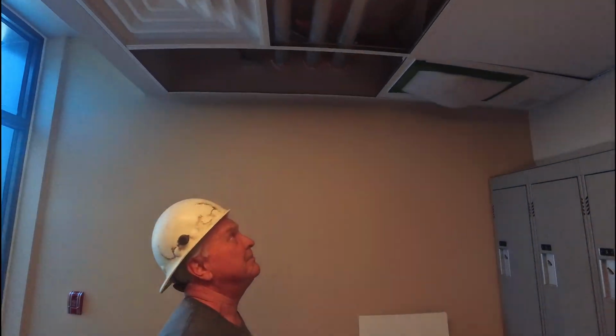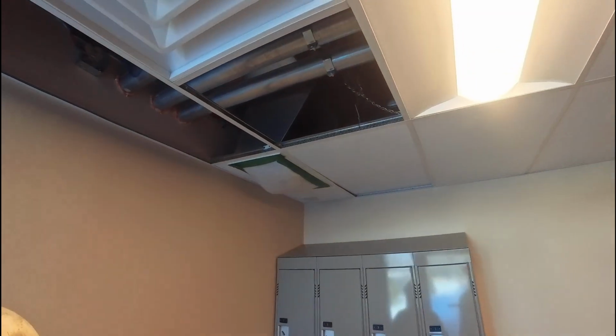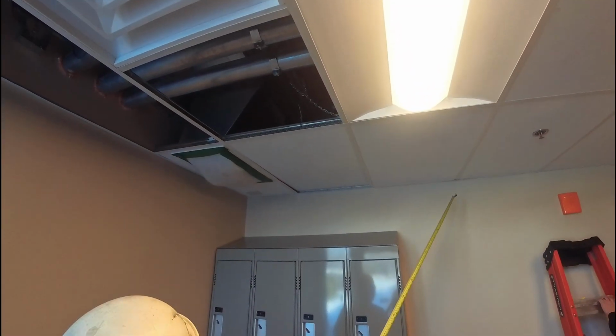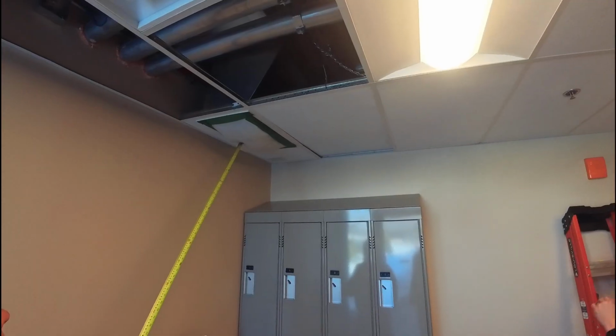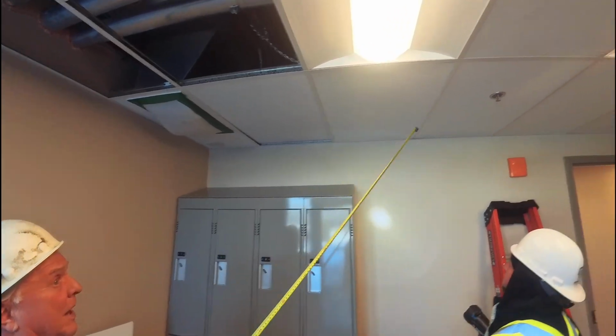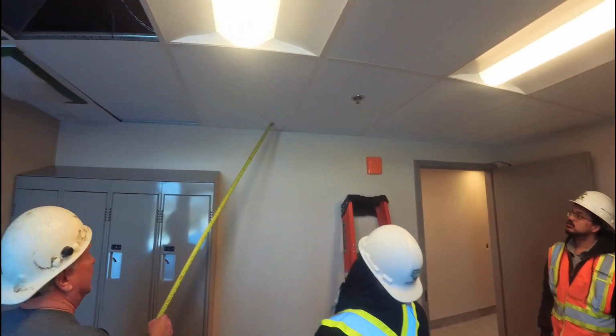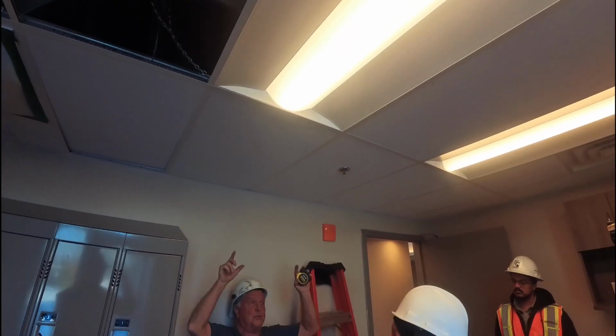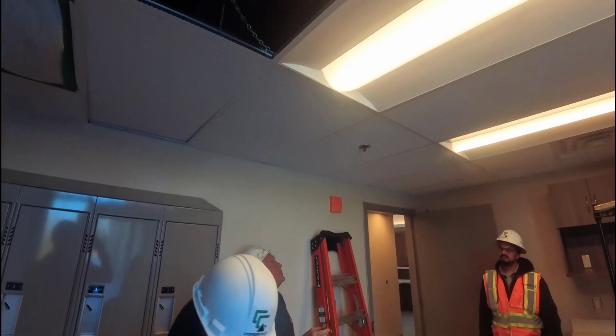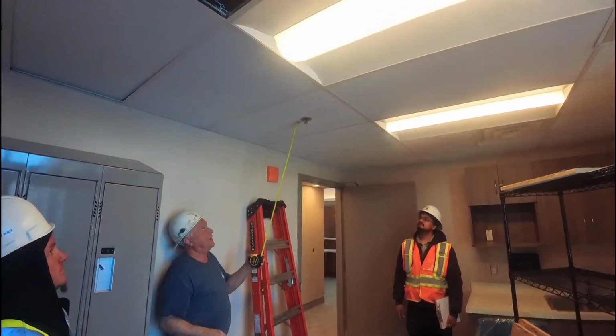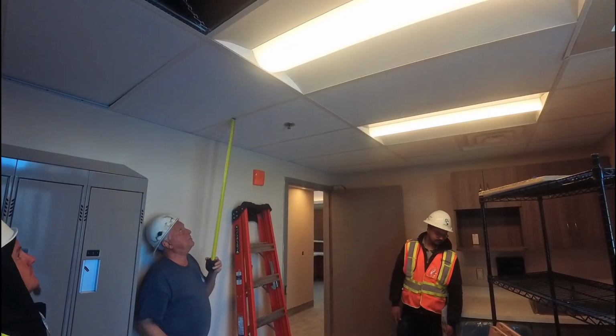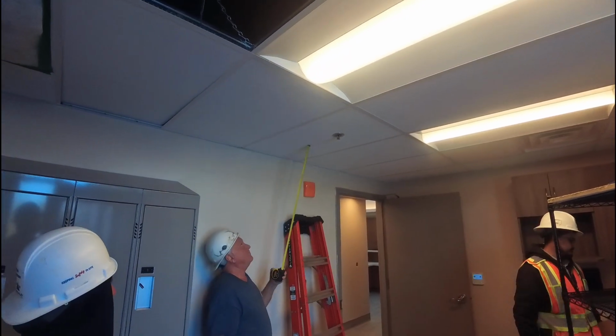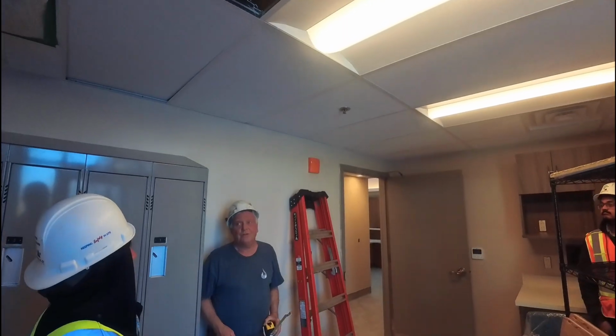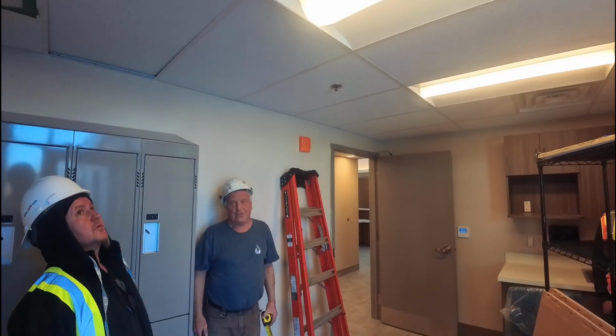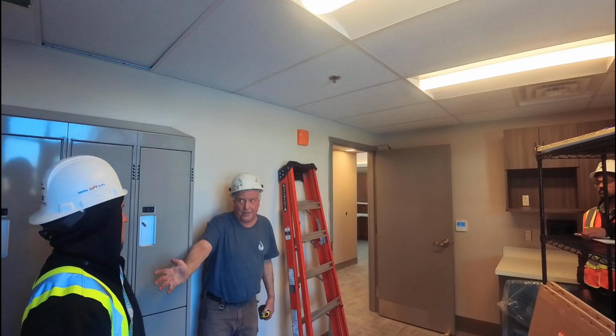The nurse's kitchen, again. The deal with him is your access is actually like, there's the return there, and the supply end is down there. Your access is actually this tile here to change the filters on this unit here. I sure hope it's not this one here and this guy has had a problem, because if it is, we'll need to put a T in here and make this portion of it removable to help assist with the changing of the filters. This is what I was telling you about the other day too.